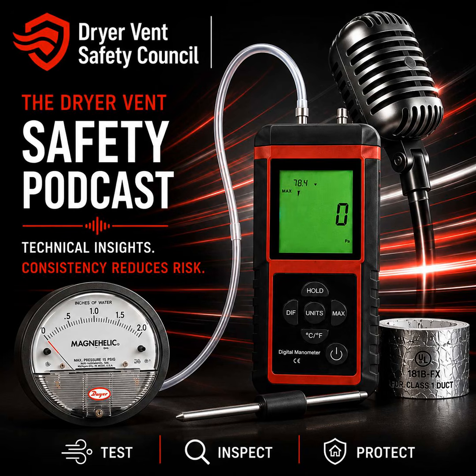Newman tested this across numerous dryers and established an essential minimum performance reference point of approximately 0.10 inches of water column. Wait, hold on. Inches of water column. We hear this jargon in HVAC all the time, but what is it literally? Oh, historically, it's exactly what it sounds like. Before digital sensors, engineers measured low pressure using a simple glass U-shaped tube, partially filled with water. Okay, so actual water. Yeah. One end is exposed to the pressure you're measuring, the other is open to the room. The pressure literally pushes the water down on one side and up on the other. And you just measure the difference. Yep, you take a ruler and measure the difference in inches. So 0.10 inches of water column means the vacuum is strong enough to pull that water a tenth of an inch.